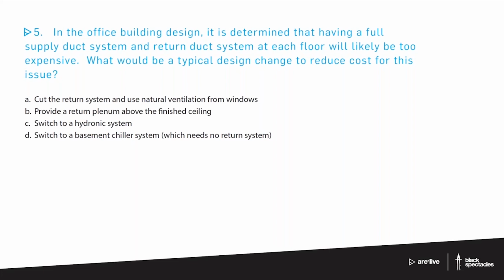Now, the trick on this question is that what we're talking about is these 2 duct systems. So we need to get the supply air to all the places that we need to get it to. Generally that's going to be towards the perimeter of the building because that's where the problem is. There are certain situations where other approaches can work, but most of the time you're going to be supplying cool air in the summer or warm air in the winter towards that perimeter wall. And if you think about it, if that's where the problem is, you're worried about losing heat or gaining heat through that perimeter wall, then you want to counteract that right where the battle is, which would be along the perimeter. It doesn't really help you a lot to dump a huge amount of conditioned air into the middle of the space, because that outside wall area is still going to be very cold or hot depending on the season.